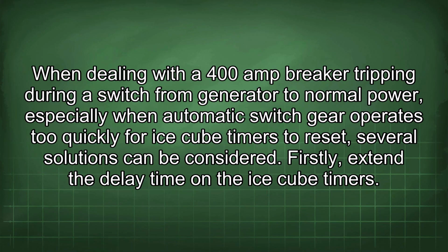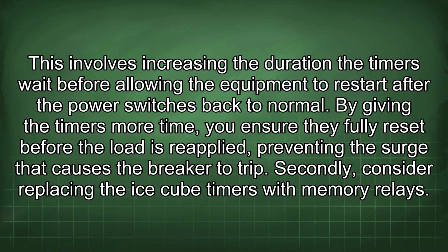When dealing with a 400 amp breaker tripping during a switch from generator to normal power, especially when automatic switchgear operates too quickly for ice cube timers to reset, several solutions can be considered. Firstly, extend the delay time on the ice cube timers. This involves increasing the duration the timers wait before allowing the equipment to restart after the power switches back to normal. By giving the timers more time, you ensure they fully reset before the load is reapplied, preventing the surge that causes the breaker to trip.